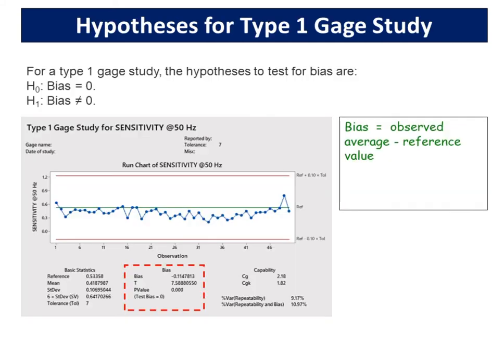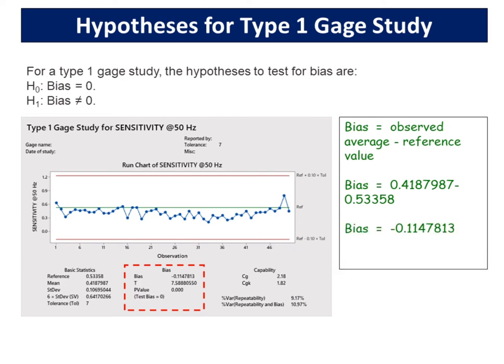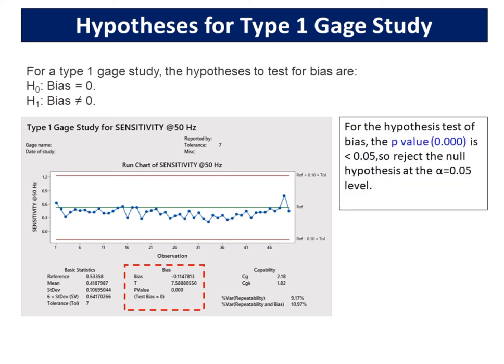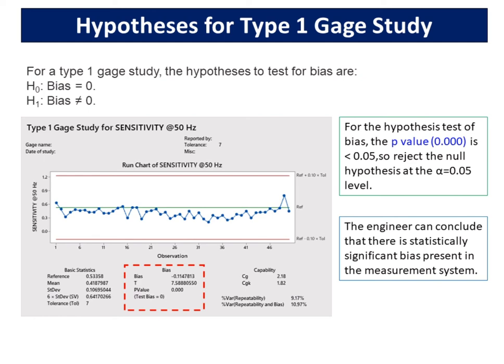For a type 1 gauge study, the hypotheses to test for bias are: the null hypothesis is bias equals 0, and the alternative hypothesis is bias is not equal to 0. Bias equals observed average minus reference value: 0.4187987 minus 0.53358, which equals minus 0.1147813. For the hypothesis test of bias, the p-value of 0.000 is less than 0.05, so we reject the null hypothesis at the alpha equals 0.05 level. The engineer can conclude that there is statistically significant bias present in the measurement system.